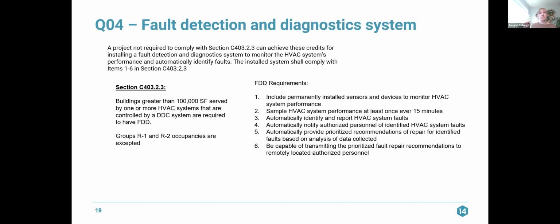So what are we requiring for these fault detection and diagnostics? You have to include permanently installed sensors and devices to monitor HVAC system performance. You have to sample HVAC system performance at least once every 15 minutes. You have to automatically identify and report those HVAC system faults, and then notify authorized personnel of identified HVAC system faults. You have to automatically provide prioritized recommendations of repair. So not only are we identifying faults, we are providing recommendations for repair based on the analysis of the data collected, and then be capable of transmitting prioritized fault repair recommendations to remotely localized authorized personnel. Could be an email, could be a text.